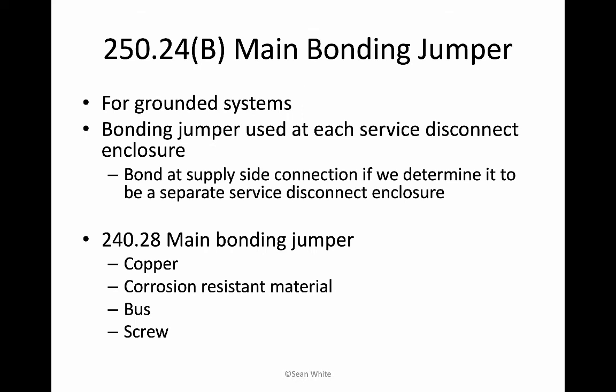We're going to talk about a main bonding jumper as in 250.24(B). And these bonding jumpers, you're bonding neutral to ground somewhere. So this, of course, is for grounded systems. A bonding jumper can be used at each service disconnect enclosure. And we're going to only have one bonding jumper per system. Also, we can bond when we're doing a supply side connection.